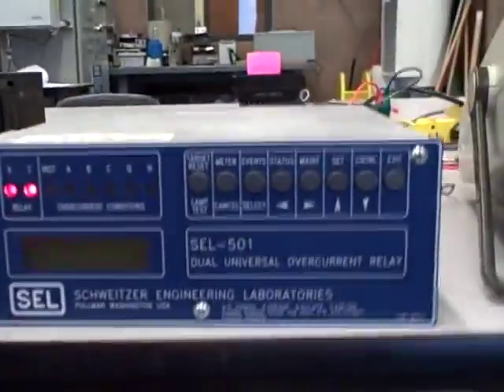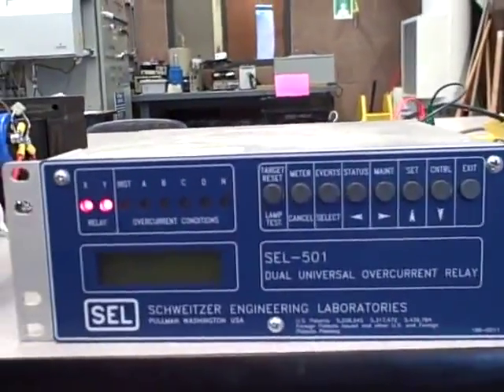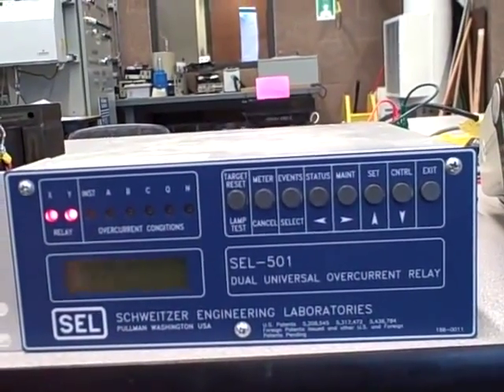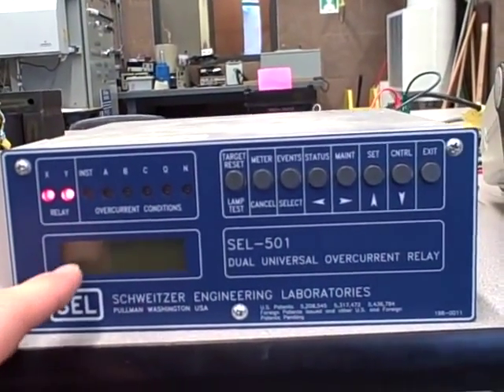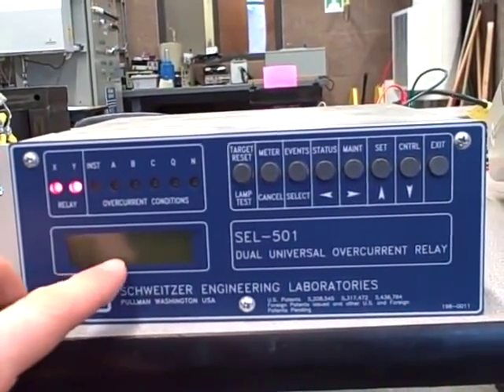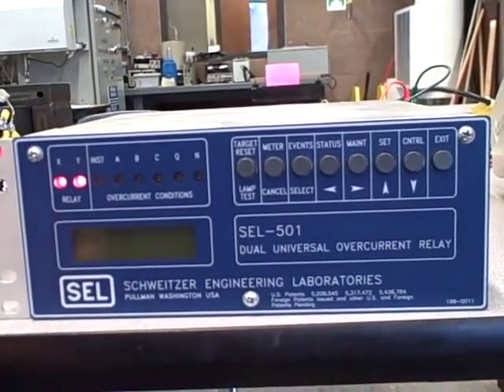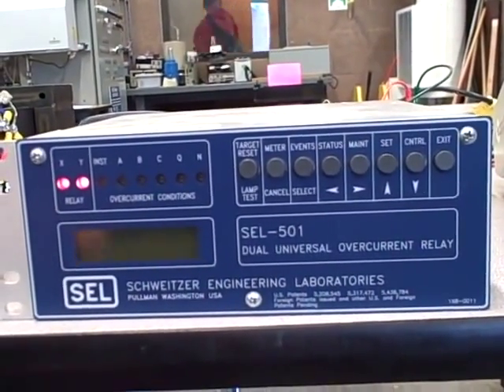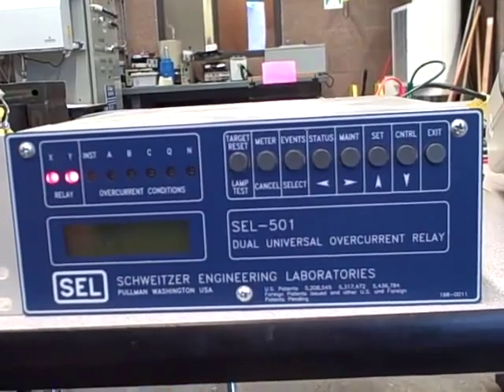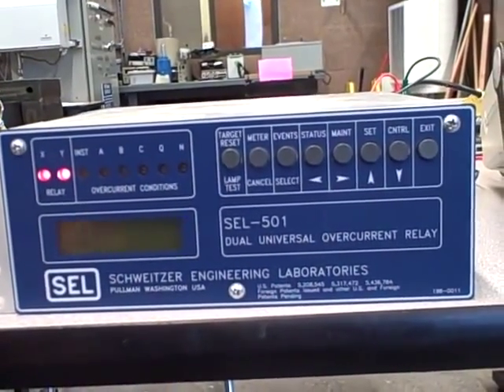If we pan back to the relay here, there's no indication it's actually timing. There's no wheel that we can watch move along. But it is actually timing the event, and it said we do have a fault. New event, a fault on X. So it detects that we're into our pickup range of current and knows there's a fault here. As mild as it is, it's taking its time to time that out.